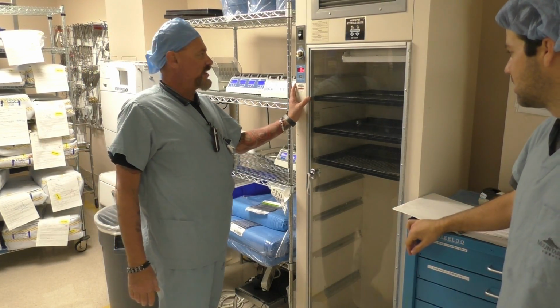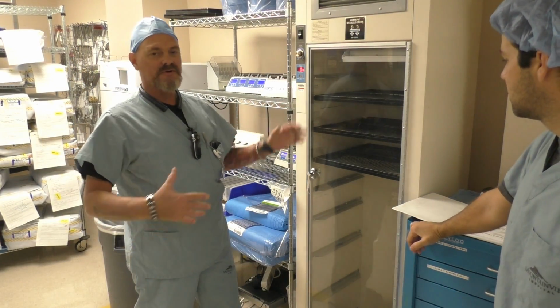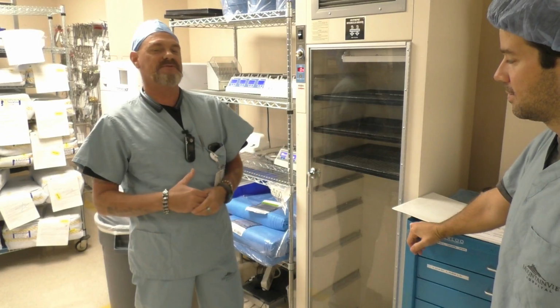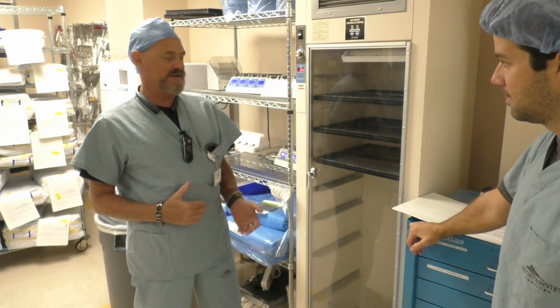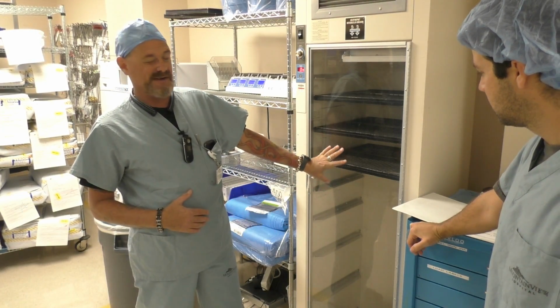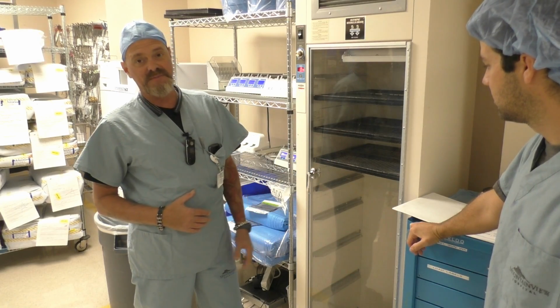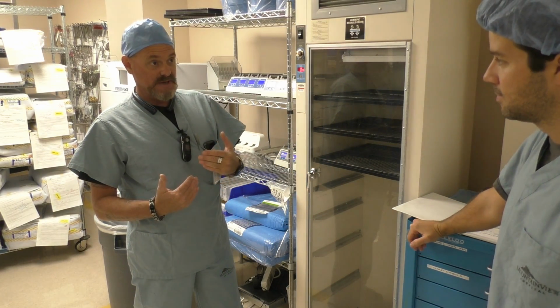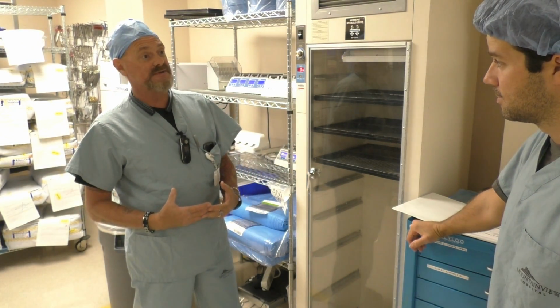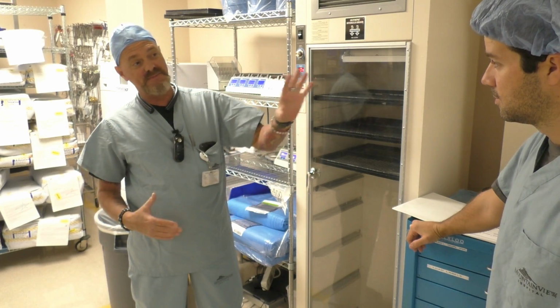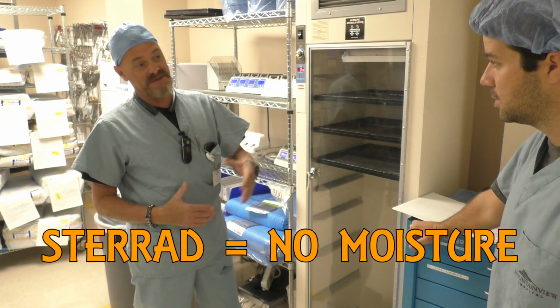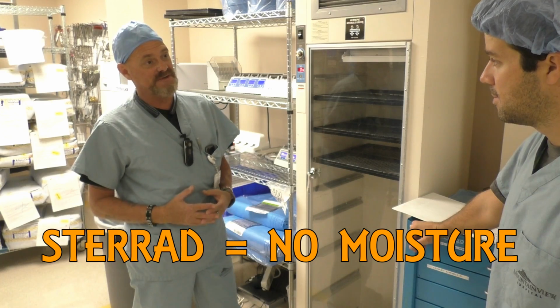So this is a dryer. So anything that's going to go into the Sterrad machines, prior to going into there, it goes in here and it'll sit in here for about 20-30 minutes to get totally dry. It cannot have any moisture going into the Sterrad. If it goes into the Sterrad with moisture, it's going to abort the cycle.